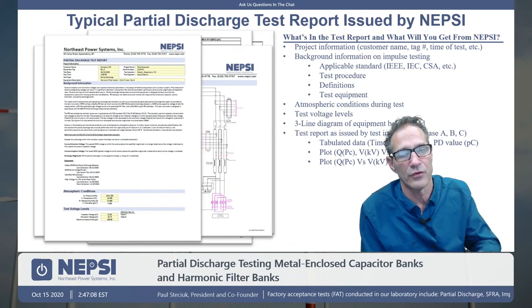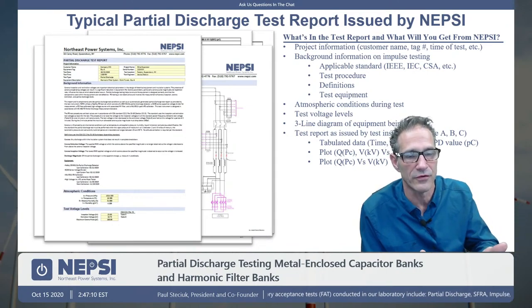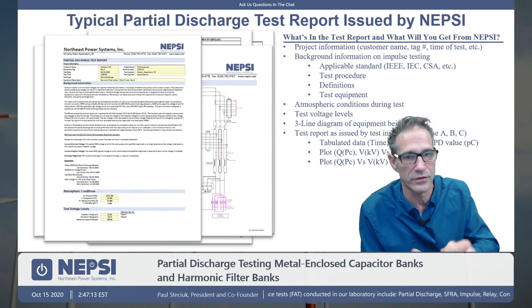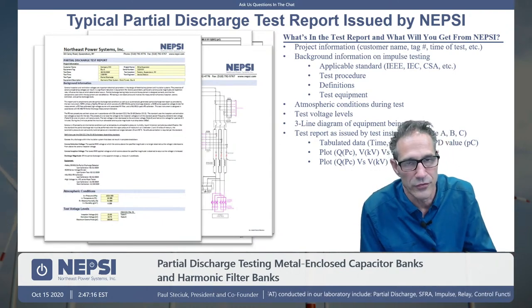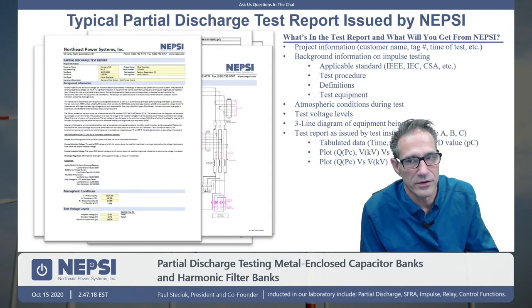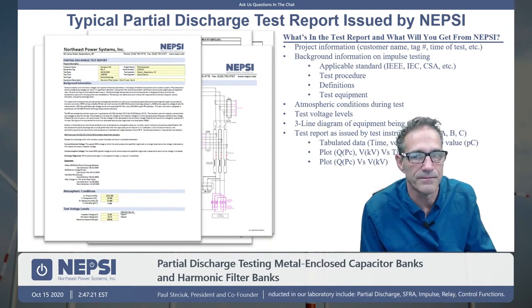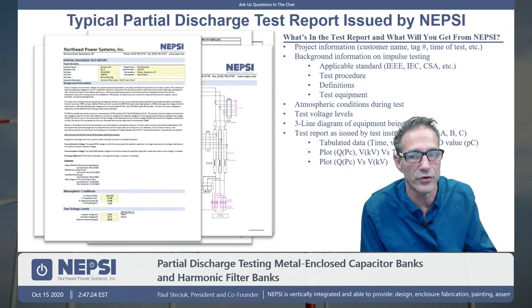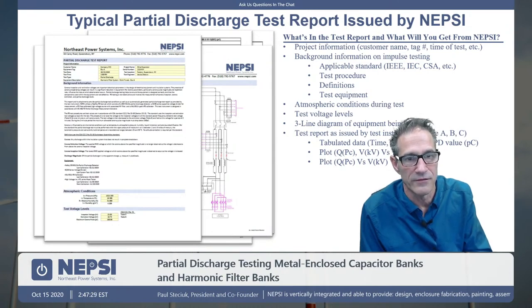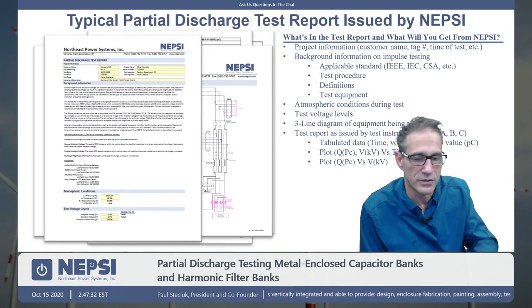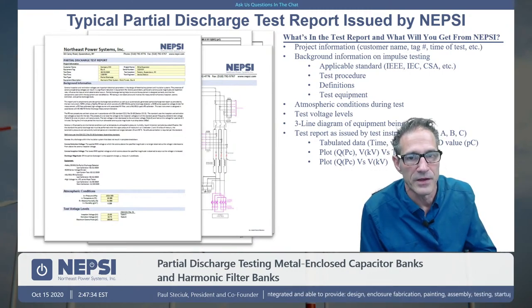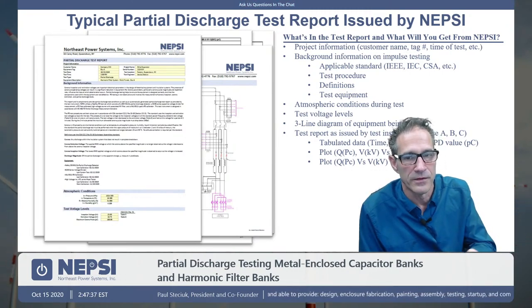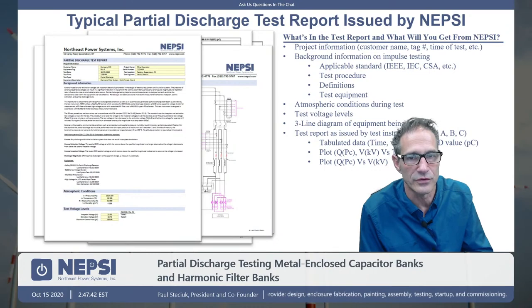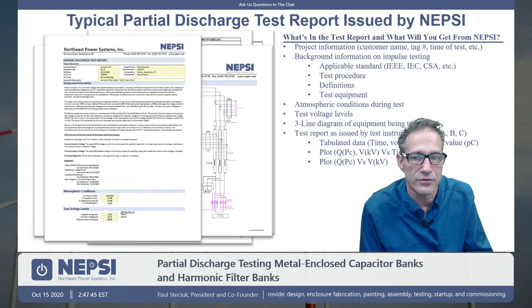Plus, we need to account for what can happen during a fault. What kind of overvoltage condition will we apply to the arrestor? So this is the way we rate the arrestor, really somewhat unrelated to the partial discharge test. The partial discharge test is really about making sure that we're partial discharge free at the operating voltage, and that if there is an overvoltage that brings us into the partial discharge region, when the voltage returns back to normal, the partial discharge will stop or cease to exist. And that's at that extinction voltage. So I hope that answers your question.